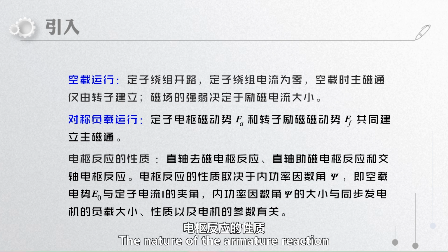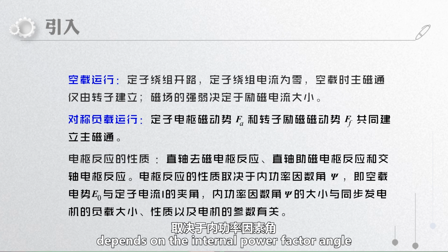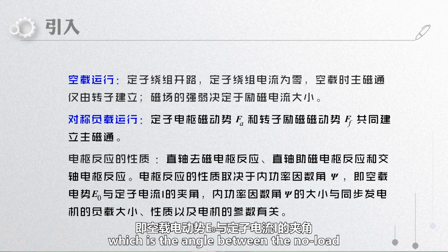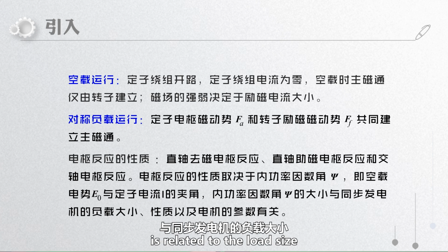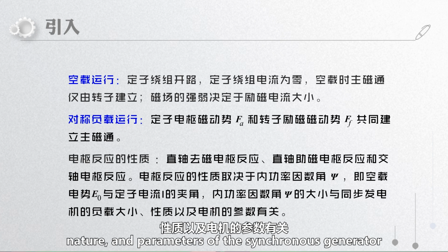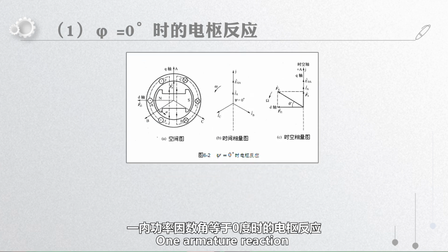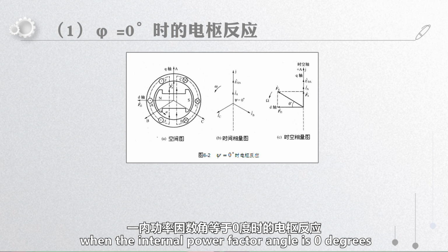The nature of the armature reaction depends on the internal power factor angle, which is the angle between the no-load electromotive force E0 and the stator current I. The magnitude of the internal power factor angle is related to the load size, nature, and the parameters of the synchronous generator. 1. Armature reaction when the internal power factor angle is 0 degrees.